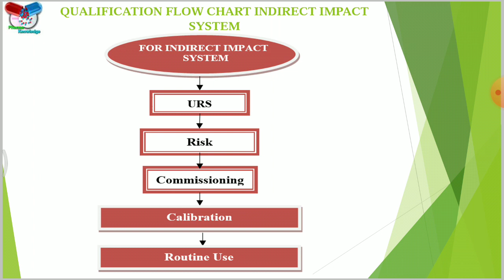The indirect system can be used for something like, in the packaging area, a conveyor belt. It is not directly related to the product, but if we mention that IQ, OQ, PQ are required for all the equipment, then obviously we would be deviating, because we will not perform the whole qualification for simple accessories or equipment used for packing of the product. This strategy is also applicable, or we can implement it, for tailor-made systems. It means the instrument is provided by the manufacturer, and there is no involvement of installation and other activity. So we can also follow this strategy for this type of instrument or equipment.